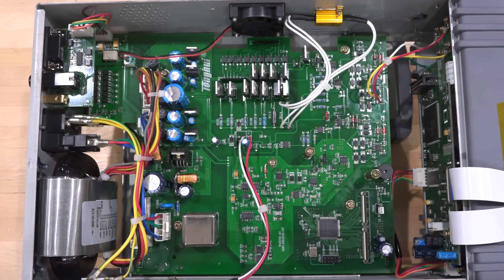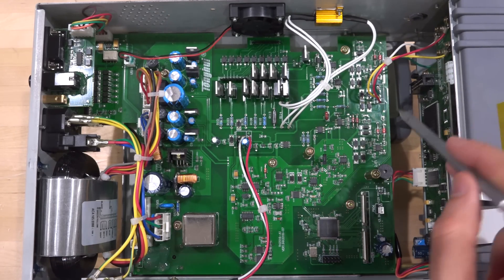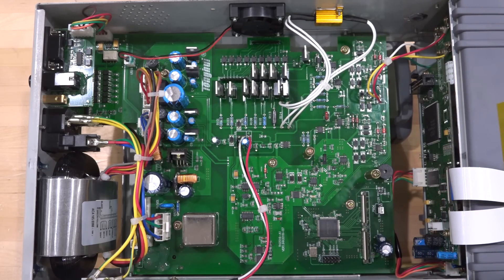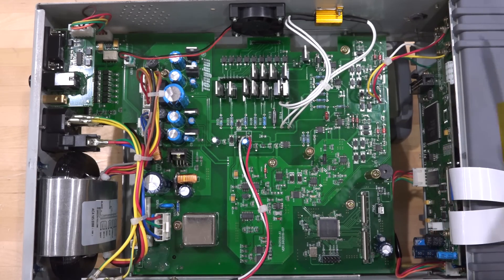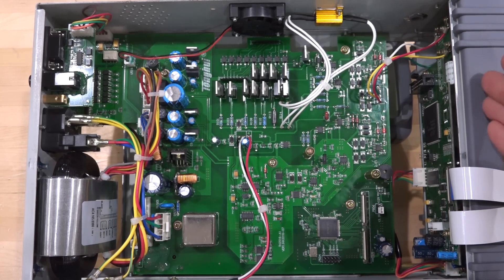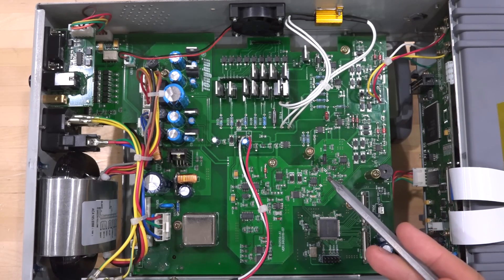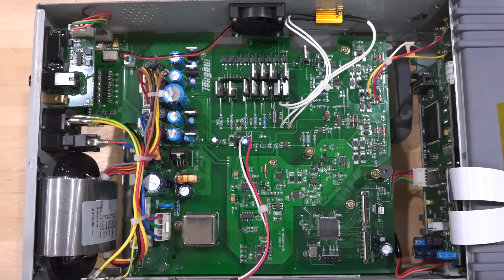Now for the rest of the instrument we do have an NXP processor here in the front panel. This is very common where the GUI processor and basically the operating system of the instrument runs in the front panel and then there's a connection from there into the main board. This is pretty much how all of these bench meters and bench instruments are now built.